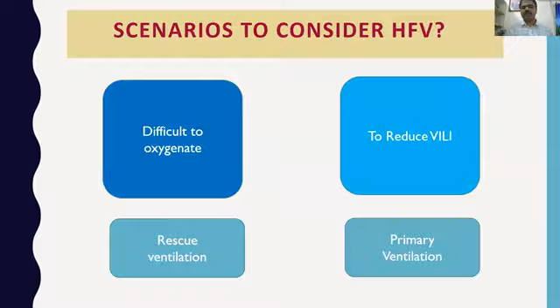So to begin with itself, you are starting high frequency to reduce ventilation-induced lung injury. High frequency is considered to be one of the safer ventilation modes, because here the dynamic strain is less. When you talk of VILI, there are two main things which cause lung damage. One is static strain, the other one is dynamic strain. And the dynamic strain is the one which causes more damage to the lungs. In case of high frequency, your static strain is more, but your dynamic strain is very less as compared to conventional ventilation. So that's why we use high frequency. We call it a gentler ventilation, and the chance of lung injury as well as strain to the lung will be less as compared to conventional. So either you are using it for rescue ventilation or as a primary mode of ventilation.